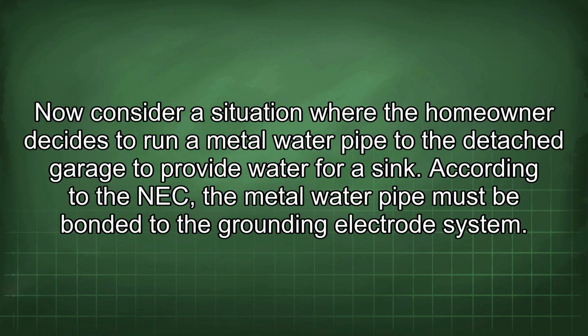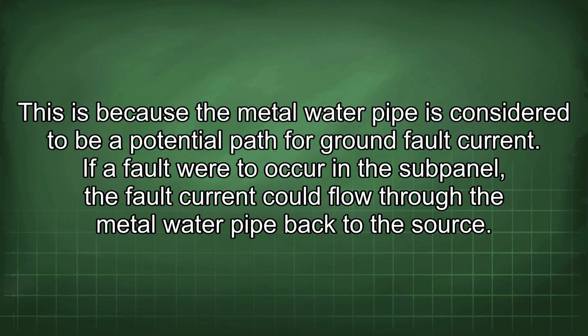Now consider a situation where the homeowner decides to run a metal water pipe to the detached garage to provide water for a sink. According to the NEC, the metal water pipe must be bonded to the grounding electrode system. This is because the metal water pipe is considered to be a potential path for ground fault current.